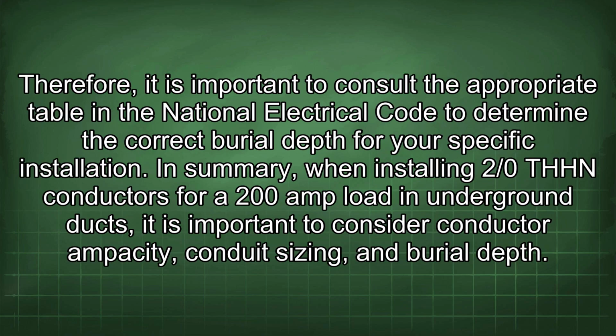Therefore, it is important to consult the appropriate table in the National Electrical Code to determine the correct burial depth for your specific installation. In summary, when installing 2/0 THHN conductors for a 200 amp load in underground ducts, it is important to consider conductor ampacity, conduit sizing, and burial depth.